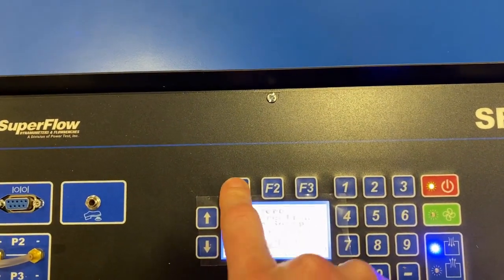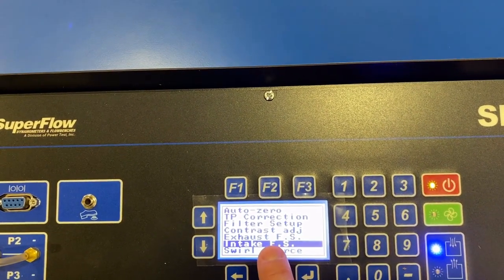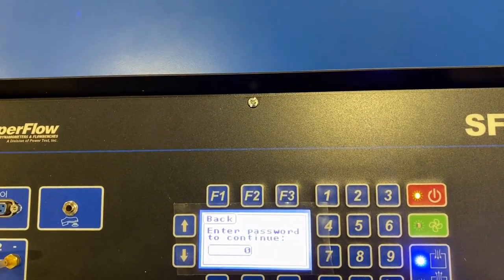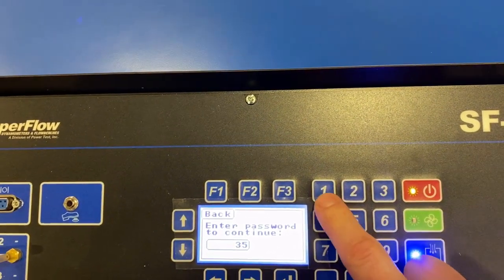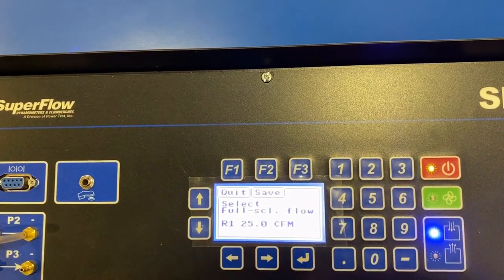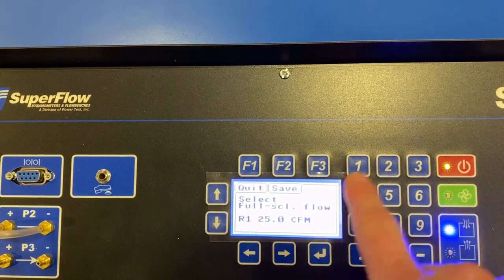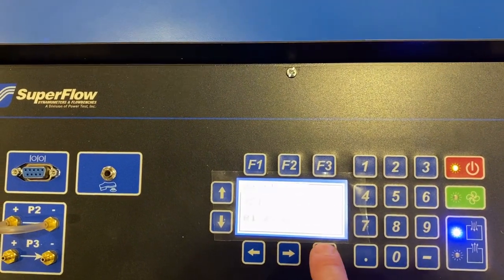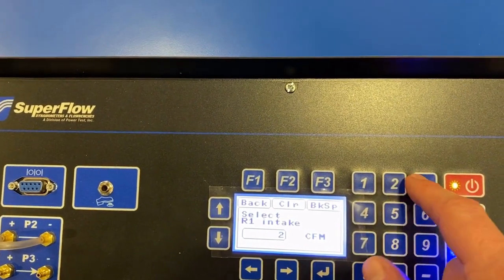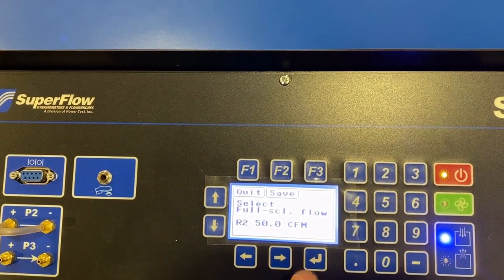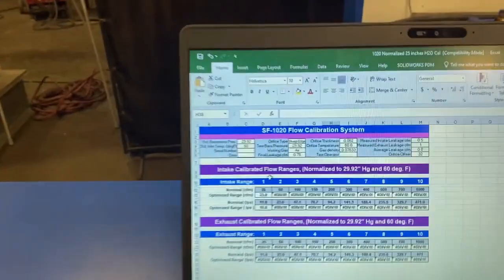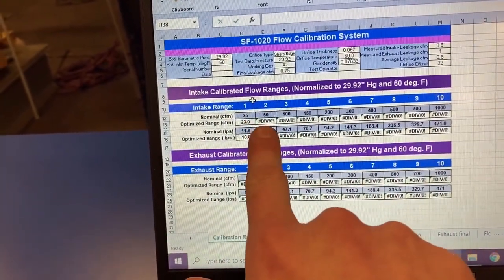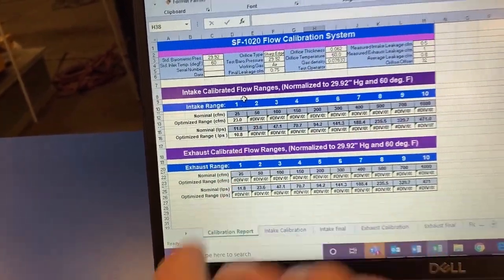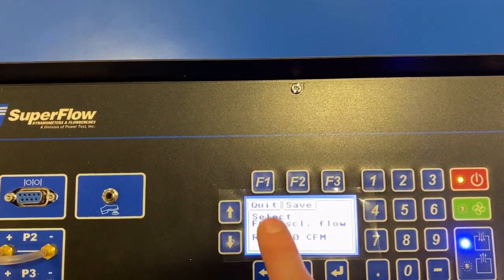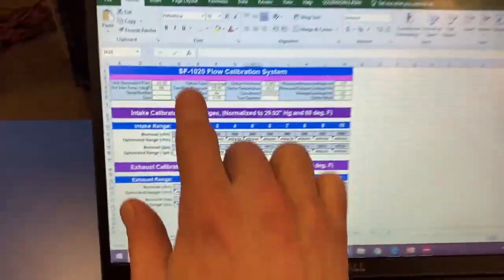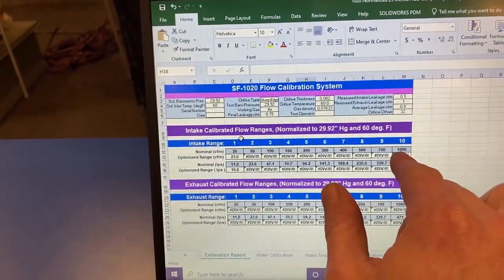Using this menu, we would configure, go to intake, since we did intake, not exhaust. Password 3512. Now you can see range 1. We would enter in 23. Sorry, I have to actually hit enter. 23. Enter. Now it's asking for range 2. We haven't done the test for range 2, but if we did, there'd be a number here. It'd be close to 50, and we would enter that number in range 2. Continuing until we have entered every number for every range, and then hit save.